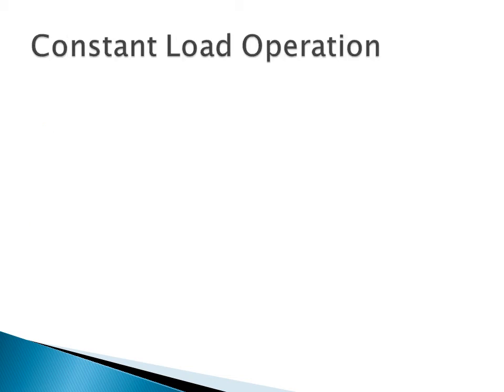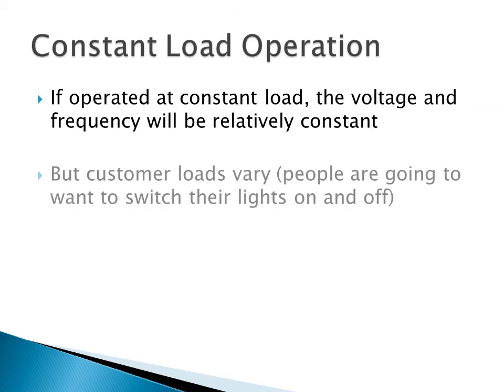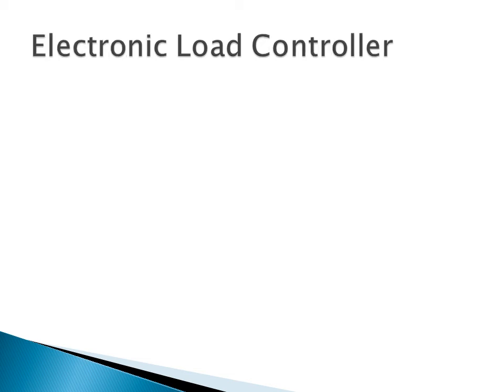So, what is constant load operation? Well, basically, it means you're running the motor at a fixed power output. And if we operate it like this, due to the characteristics of the induction motor, the voltage and frequency will stay relatively constant, which is desirable for a generator. However, the customer loads will vary, and people are going to want to change their loads. People are going to want to have the fridge come off and on, fans on and off, TV, etc. So, how do we maintain a constant load at the generator to ensure that the voltage and frequency remain generally fixed?